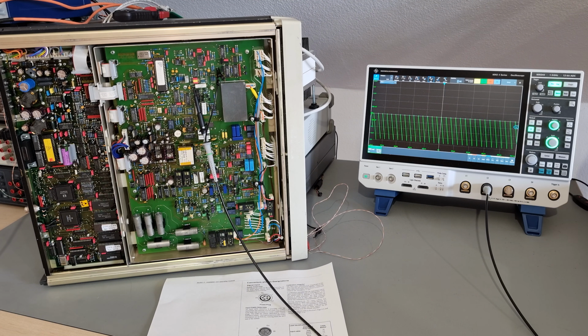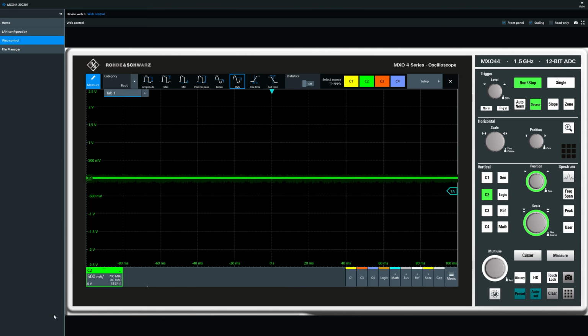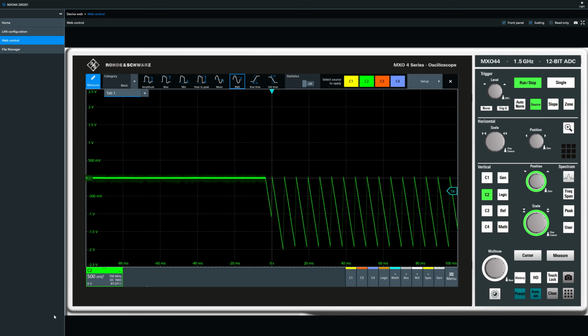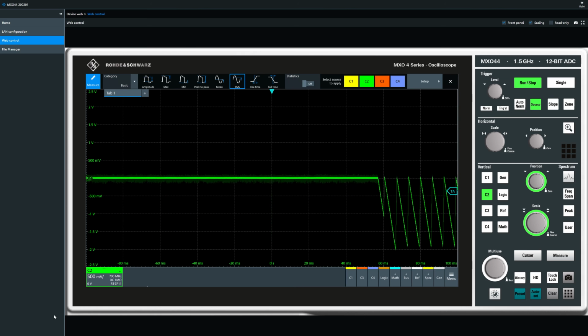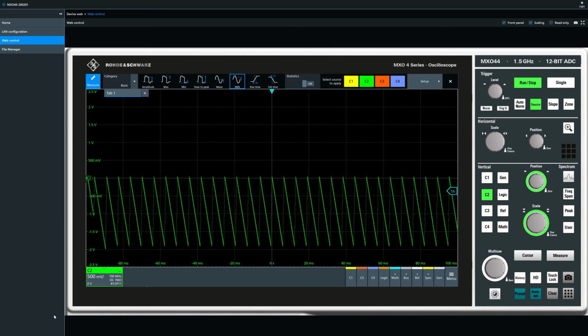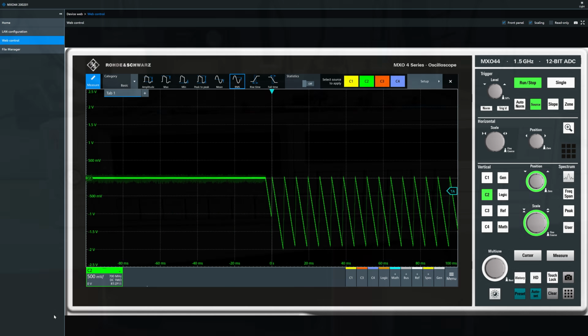Yeah, this is not quite as unhinged as that simultaneous multi-run-up, multi-run-down algorithm in 3458As, and it doesn't have to be. This device relies on spot calibrations and therefore has no need for linearity. Only low noise would be good.